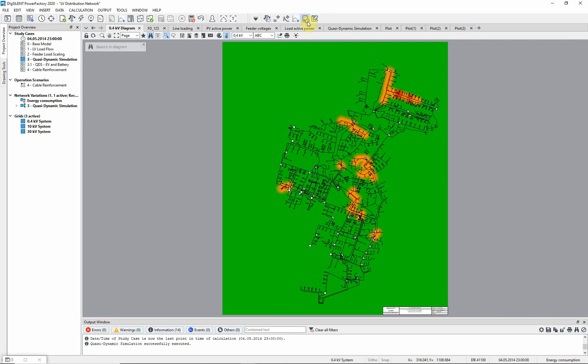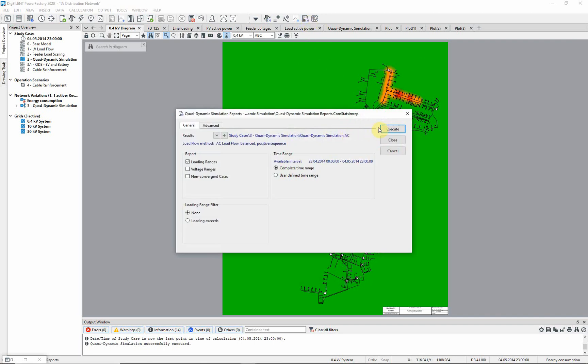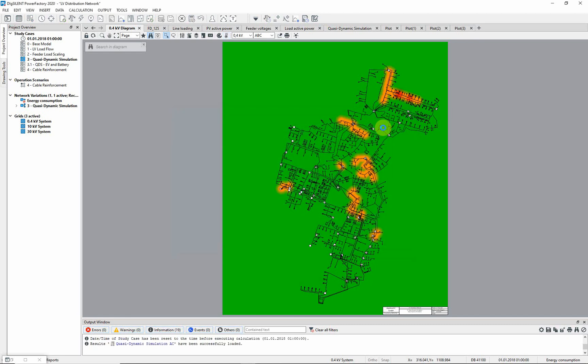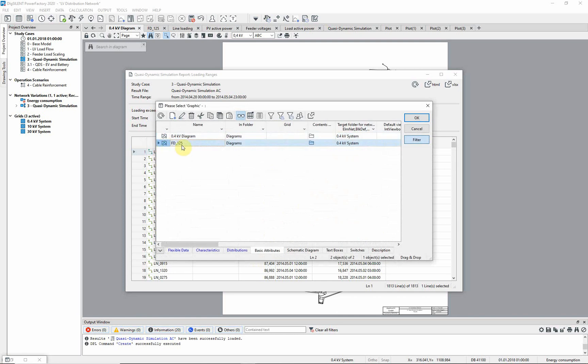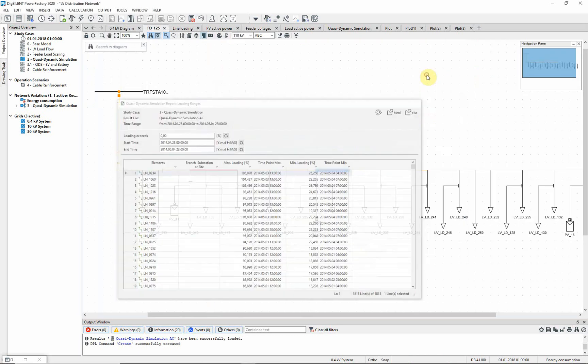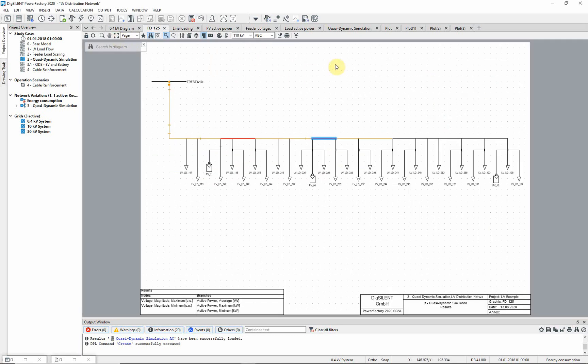Now run the quasi-dynamic simulation loading ranges report. Select loading ranges and choose the complete time range, then execute the report. Three lines are loaded above 100% of their maximum loading. Mark the most heavily loaded line in the graphic and choose the feeder schematic — the heavily loaded section of line is marked.